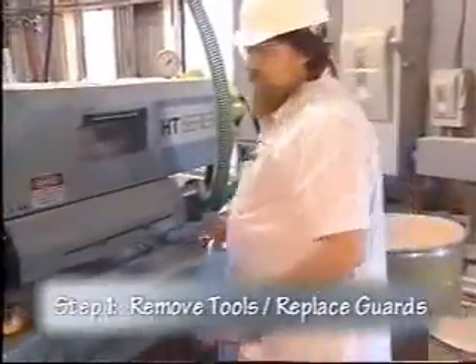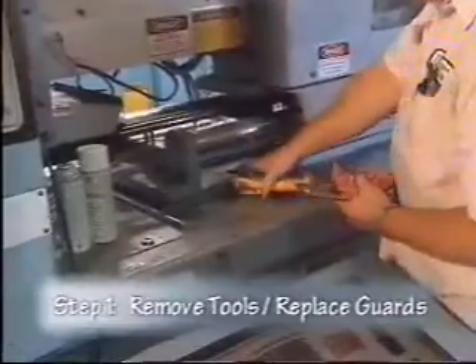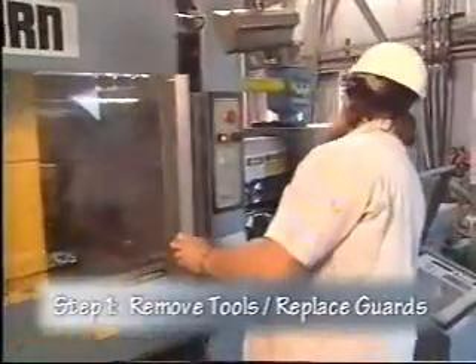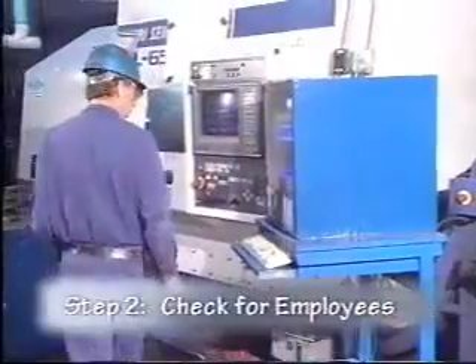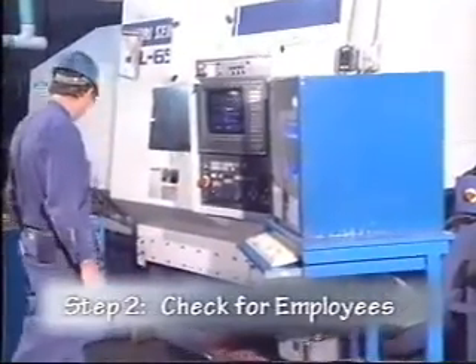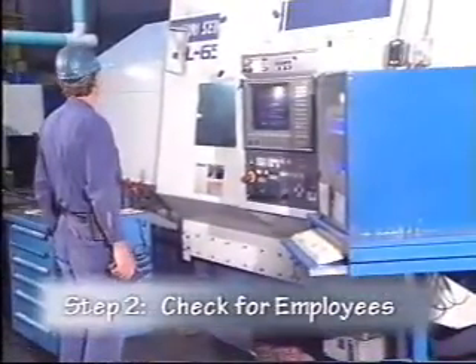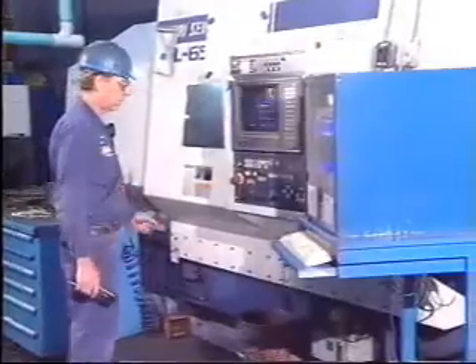After the service work is finished, here are 5 steps to release the equipment from lockout-tagout. First, check to make sure that all tools have been removed and all the machine guards are back in place. Check that all employees are clear of the machine. If you can't see inside a piece of equipment, take a head count.